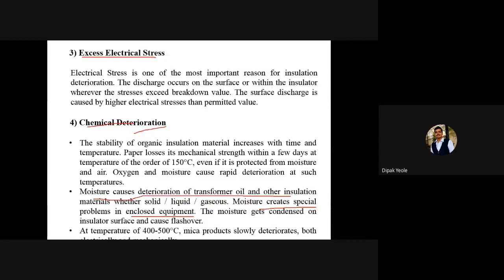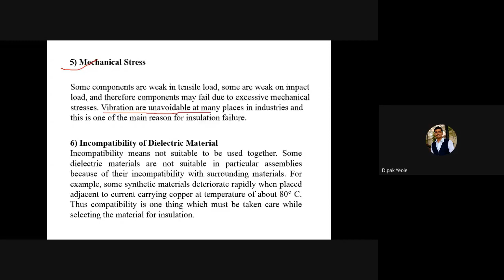Similarly, if our equipment is packed, there is no air circulation or air ventilation available, so moisture is going to develop, and because of that moisture there is formation of sparks inside the insulator. Yes. The fifth cause is mechanical stress. Vibration plays an important role in this mechanical stress. We cannot avoid this vibration, but we can minimize it by having a perfect foundation.